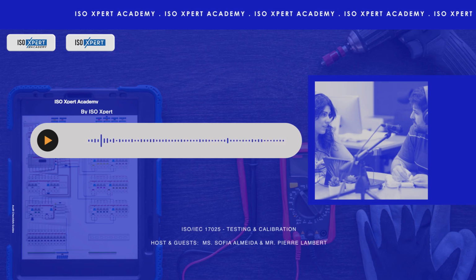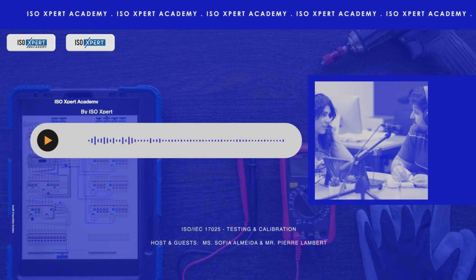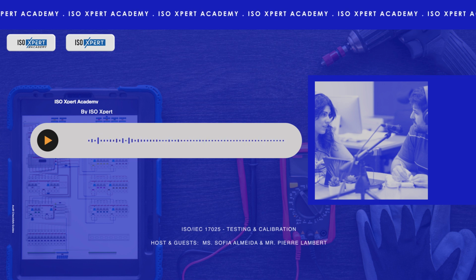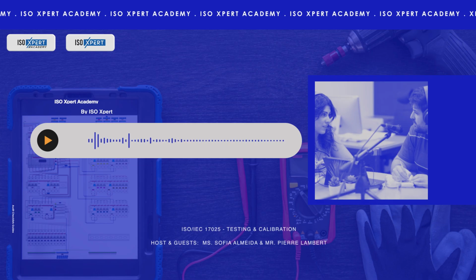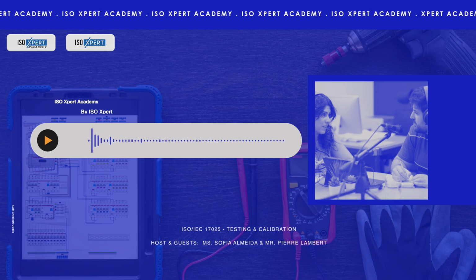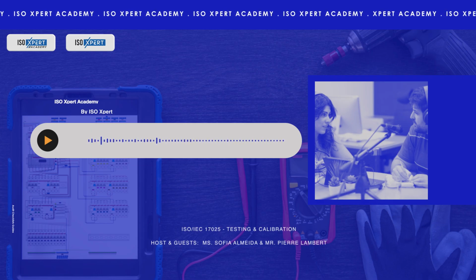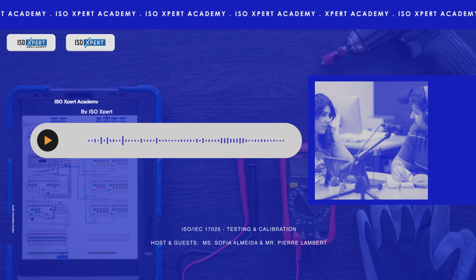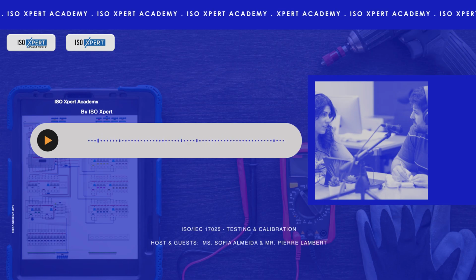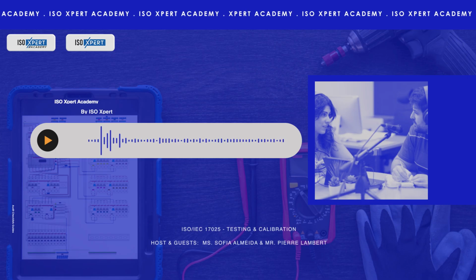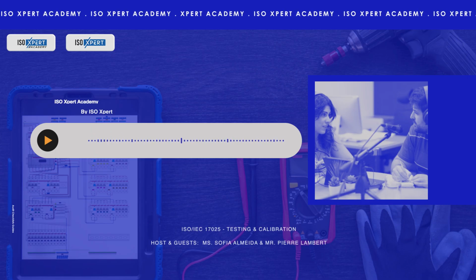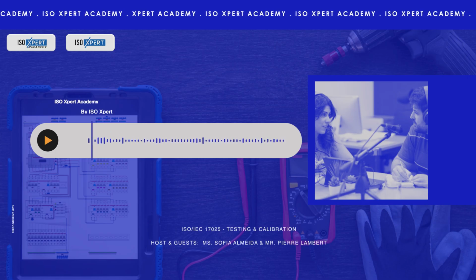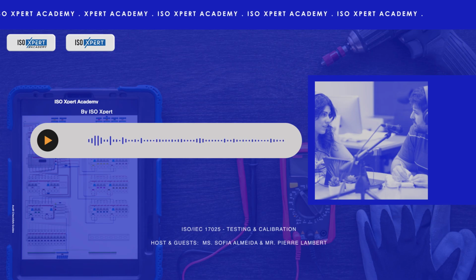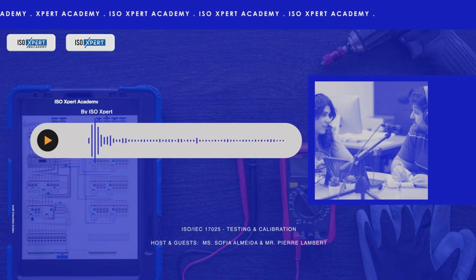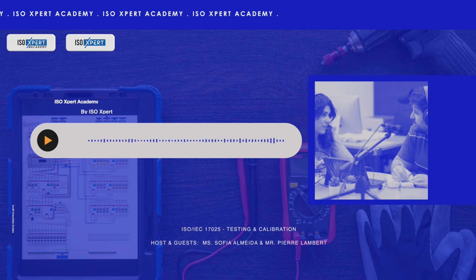Okay. Now, a truly effective system doesn't just react when something goes wrong, it tries to anticipate problems, right? That sounds like Clause 8.5, actions to address risks and opportunities. That's exactly right. Labs are expected to proactively think about and manage potential risks. Risks like what? Anything that could jeopardize their impartiality or affect the validity of their results. Maybe a key piece of equipment failing or losing a critical supplier, or even bias creeping into a process. So they need to identify these. Identify them, analyze them, and plan actions to mitigate them.